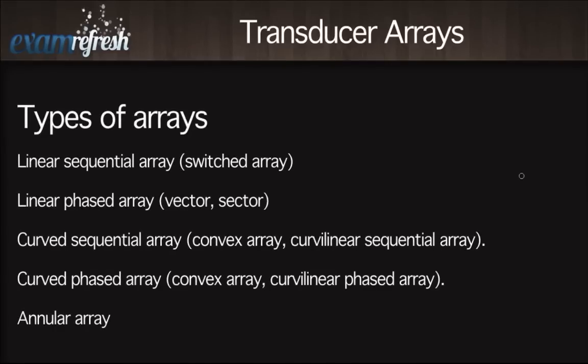Welcome to this week's lesson. We'll be speaking about transducer arrays. This can tend to be a little confusing because the names are the same and then they add one qualifier that kind of changes what the actual transducer array does. There are a few different types of arrays we'll go over today: a linear sequential array, which is a switched array; and a linear phased array, which would be a vector giving us a sector image.